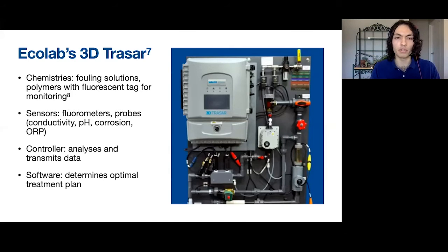Besides the fluorometer, we also have other probes that measure conductivity, pH, corrosion, and oxidation reduction potential. All of these really just tell us if there's any corrosion happening in the system. Since corrosion is an electrochemical reaction, all these can give us a pretty good idea of corrosion happening in the system. All the data that's collected by these sensors gets analyzed by a controller, which is the big box on the top left of the picture.